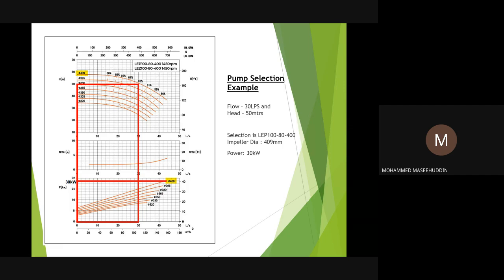Because if the net positive suction head actual is less than the net positive suction head required, then the pump will still run, of course, for maybe 1 year or 2 years. Then there will be a problem of cavitation in the pump itself. And due to cavitation, there will be damage to the mechanical seal, the bearings, the shaft. It could be anything, the impeller. So it damages the complete pump.